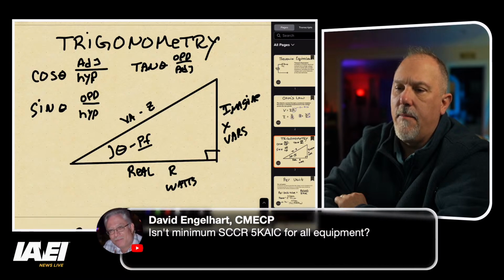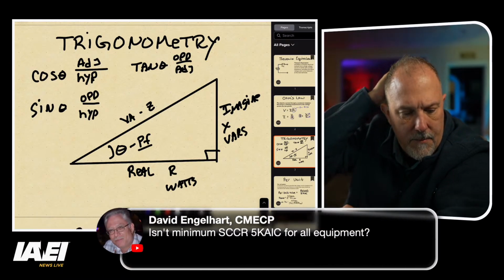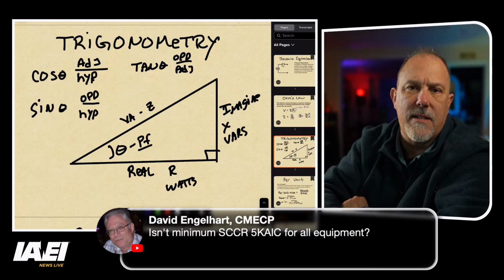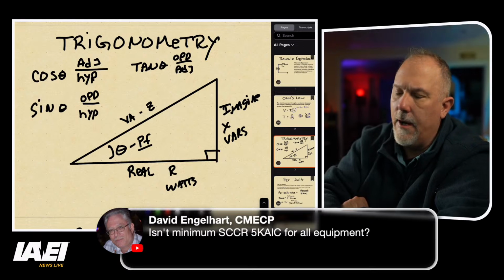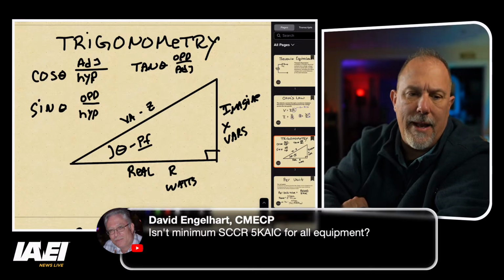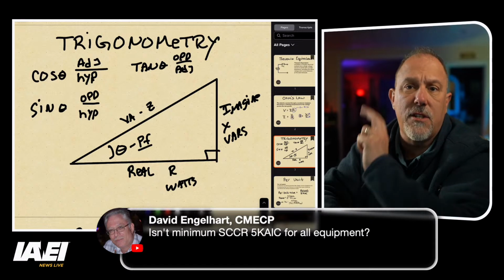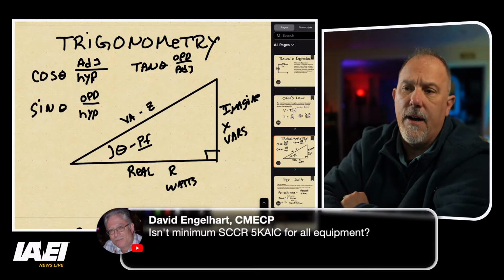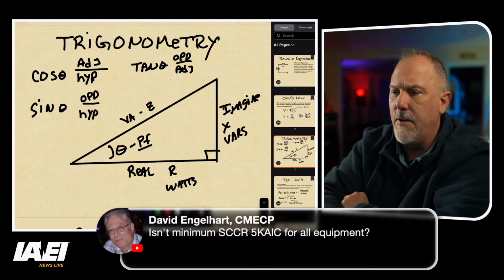Isn't it a minimum of 5 kA? You know what? Not necessarily. I know a GFCI receptacle that hasn't gone through Supplement SA has a 2 kA short circuit current rating. David.